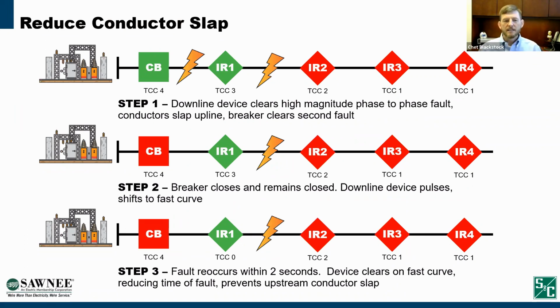Once the interrupter detects system voltage, it tests. If it detects the fault, it tests all the way to lockout successfully and doesn't operate the circuit breaker. If it's a recurring fault, then it initially tests with no fault. If that fault reoccurs within 2 seconds, it trips instantaneously, allows less energy through the system, doesn't have enough fault current or time. It's really the same fault current, but less time, and able to have the phases slap, and it operates all the way to lockout without subsequent feeder breaker operations.